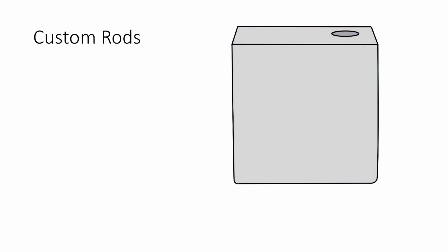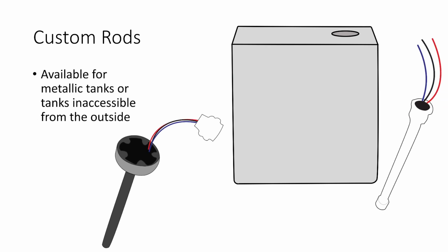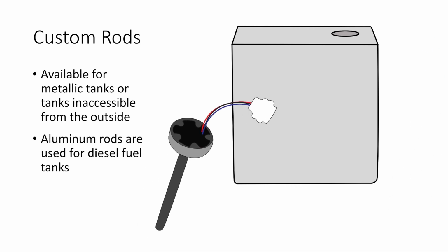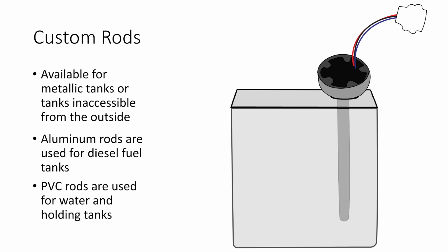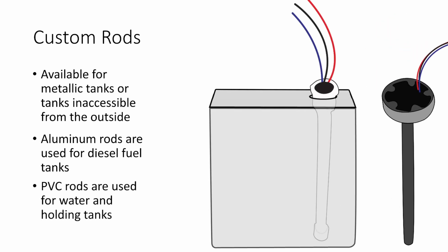Custom rods. For metal tanks or tanks that are not easily accessible on the outside, you will need to order a PVC rod or a diesel fuel sensor rod. Aluminum rods are used for diesel fuel tanks, and PVC rods are used for water and holding tanks.